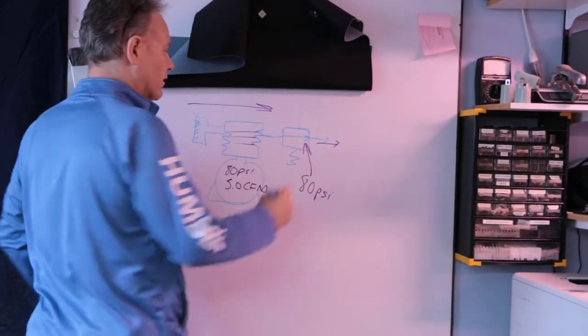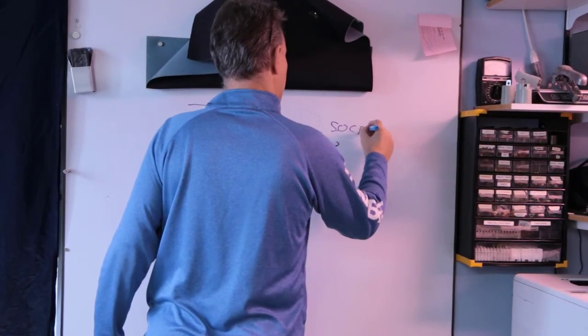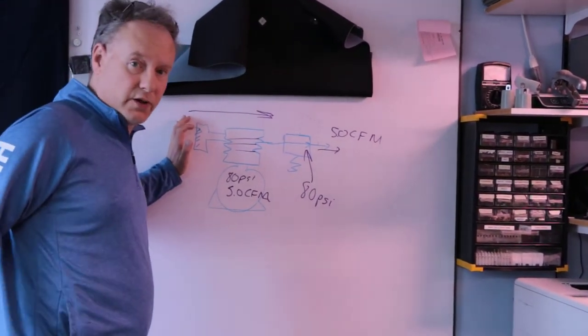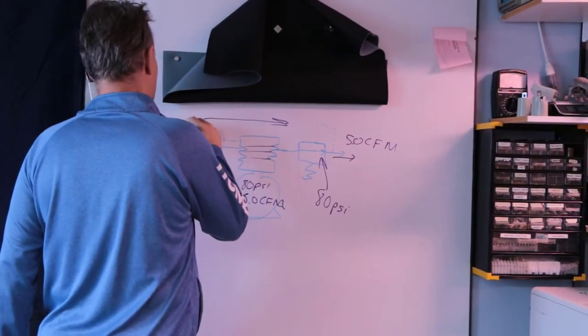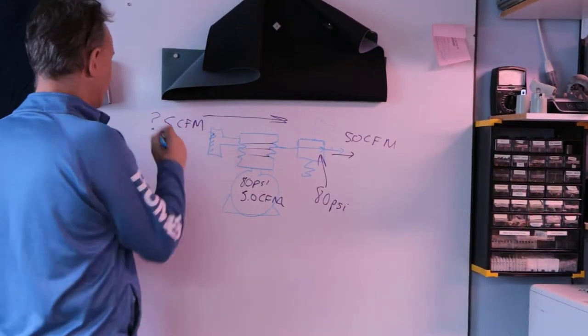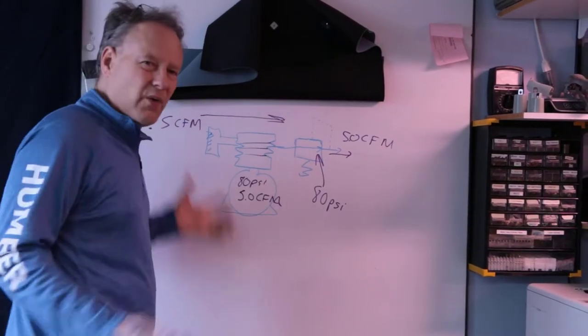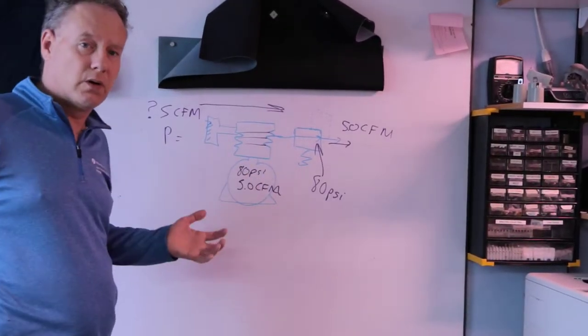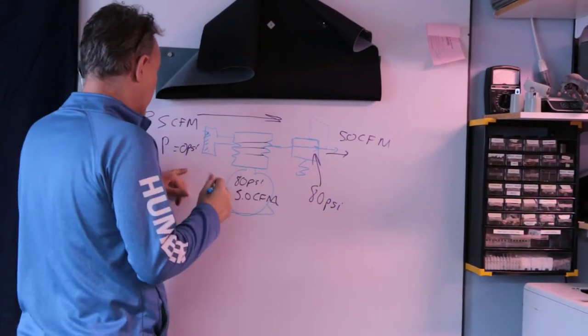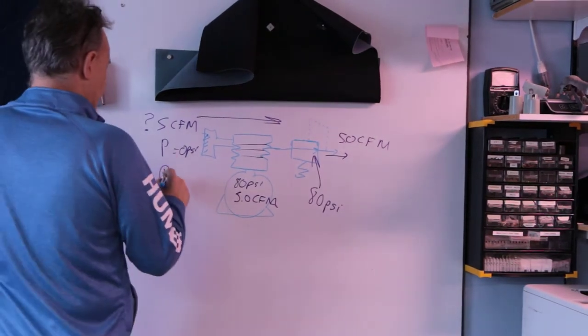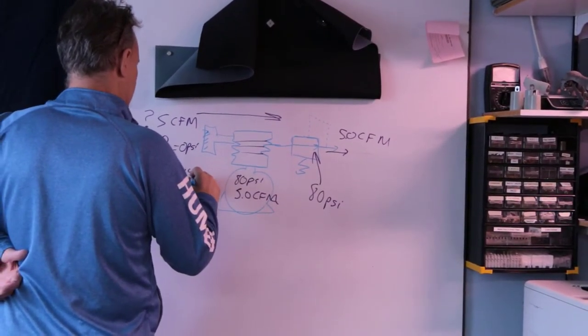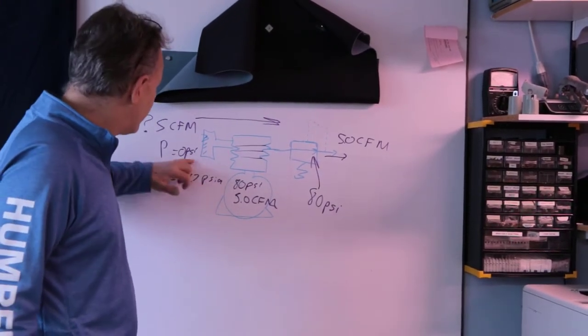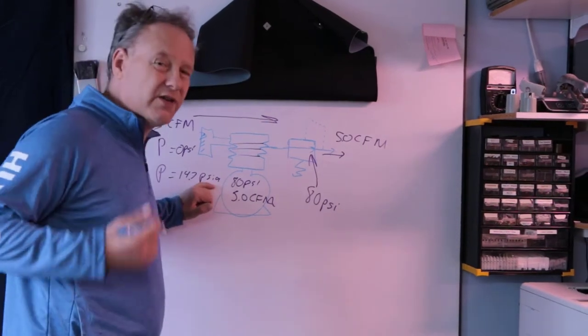What does that mean for the air coming in? The air coming in is standard cubic feet per minute. We don't know that exact value, but I just want to unpack what's going on. We know the pressure at the inlet is zero PSI gauge, which means 14.7 PSIA — atmospheric pressure. Two different pressures, and whenever we do any formulations, we have to always convert to PSIA because of the gas laws.